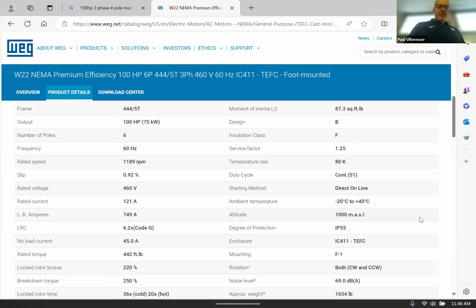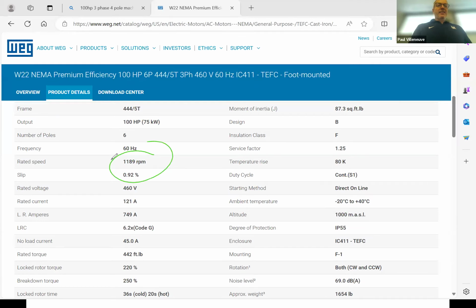I'm really interested in this, let's see if I can annotate that. Why is that so interesting to me? Because this tells me, and you got to read it carefully, that this machine has a rated speed of almost 1190 RPM. That's when it puts out 100 horsepower. It puts out more than 100 horsepower at less than that, but it's not going to last very long unless you have really good cooling to be able to provide that. So this is running at 1189 RPM.